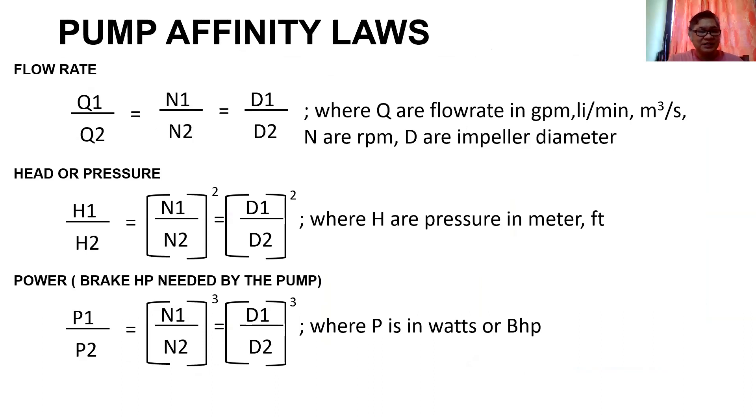The flow rate, the head, and the power of the pumps, fans, and blowers. The flow rate, the ratio of the flow rate Q1 over Q2 is equal to the ratio of the speed N1 over N2 and the diameter of the impeller D1 over D2.